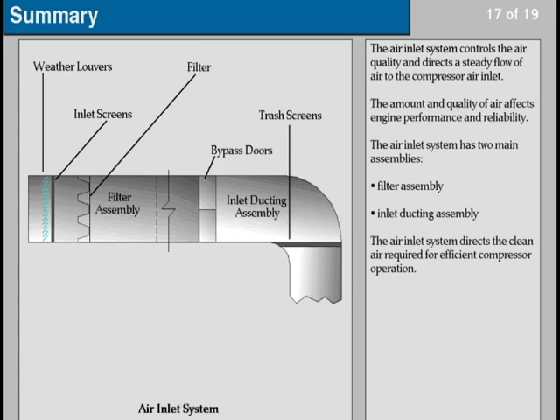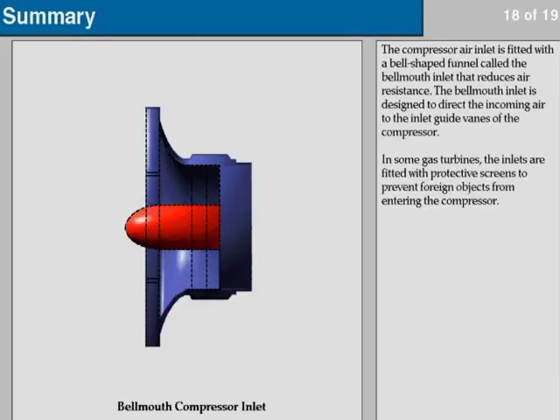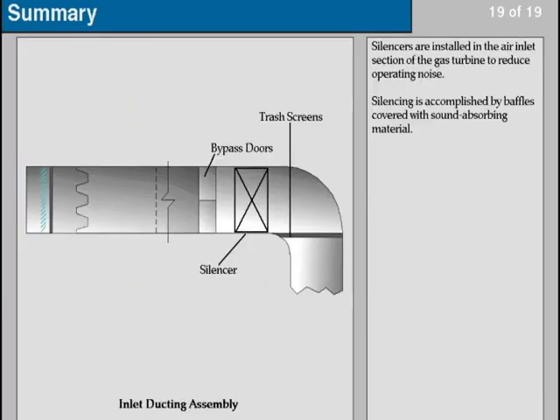The air inlet system directs the clean air required for efficient compressor operation. The compressor air inlet is fitted with a bell-shaped funnel called the bellmouth inlet that reduces air resistance. The bellmouth inlet is designed to direct the incoming air to the inlet guide vanes of the compressor. In some gas turbines, the inlets are fitted with protective screens to prevent foreign objects from entering the compressor. Silencers are installed in the air inlet section of the gas turbine to reduce operating noise, accomplished by baffles covered with sound-absorbing material.